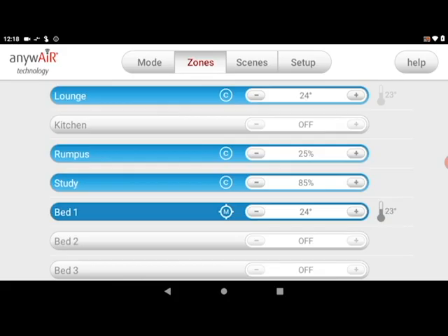This is the logic of the constant zones. Constant zones may be opened automatically if you're running less zones than you've set as the constant zones. Zones which have been turned on automatically may turn off automatically as well once you start turning on other zones manually. So constant zones are a great way to achieve the right amount of airflow across the home, however not having too much pumping through a small outlet in a limited space.